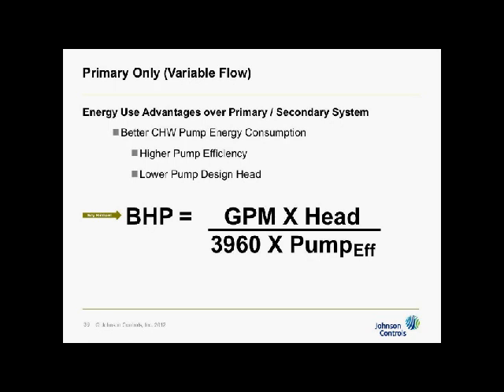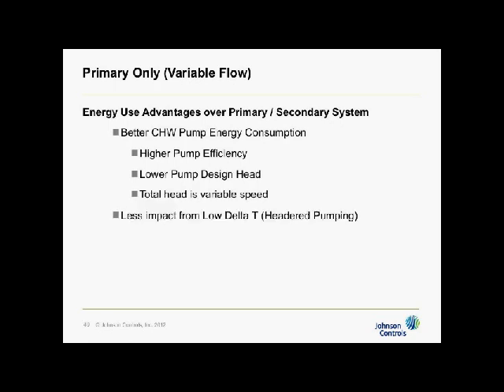There's a third reason for energy savings that most people don't recognize, and that is that if I have a third of my head in the primary that is all constant flow, constant speed, there's not much savings there, as opposed to the secondary where 2/3 of it's variable head, and I get a lot of VSD savings. Now I've got the entire plant that's VSD, and all of the head is variable, so I've got that savings too. So there's three reasons why we have an energy use advantage over primary secondary.